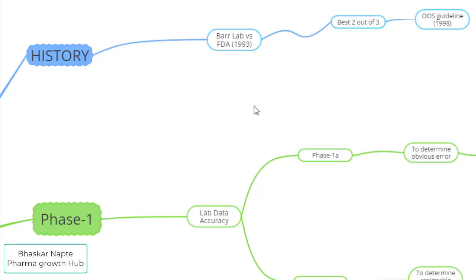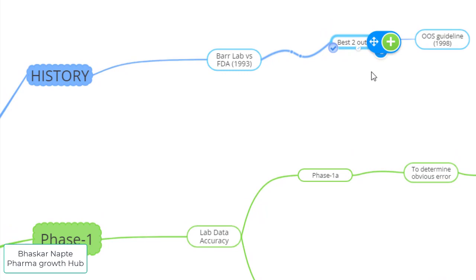What was the practice followed by Barr Labs? If there was an out of specification result, Barr Labs used to conduct testing for the same sample two more times, so there would be three results available — the first OOS result and two retesting results. Barr Labs used to select the two best results out of these three. If both retesting results met the specification, Barr Labs would release the batch. But US FDA had a concern about this approach, saying it was not scientific and that no reference was provided by Barr Labs.